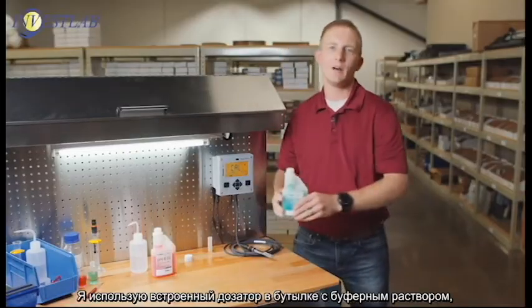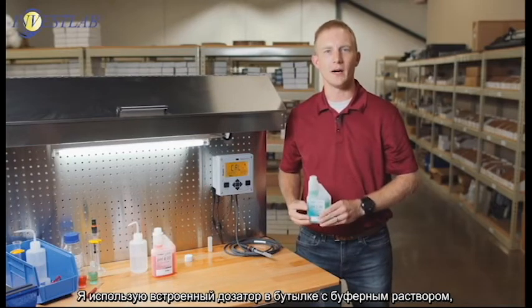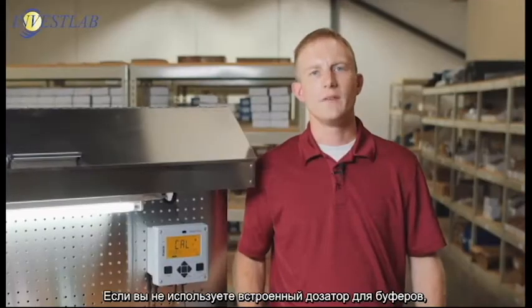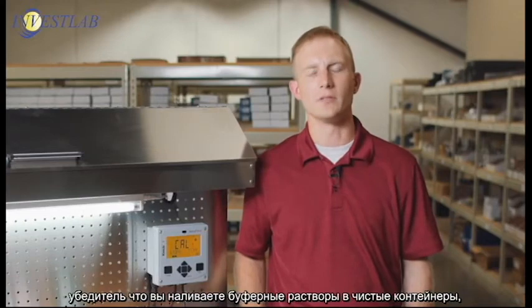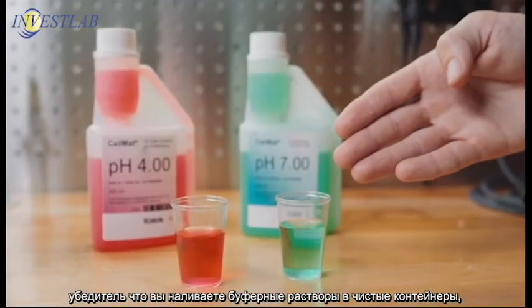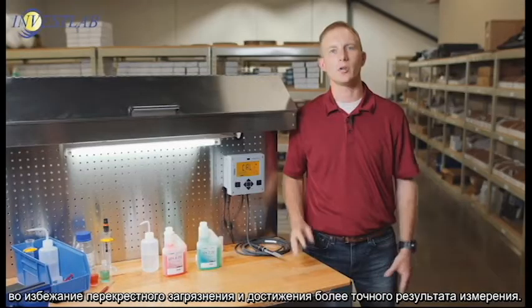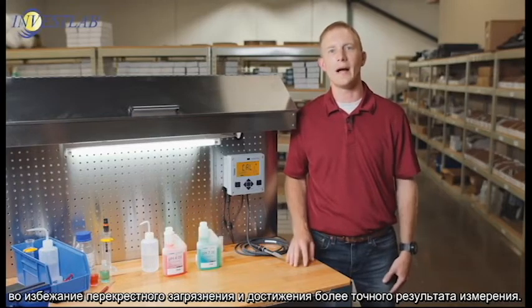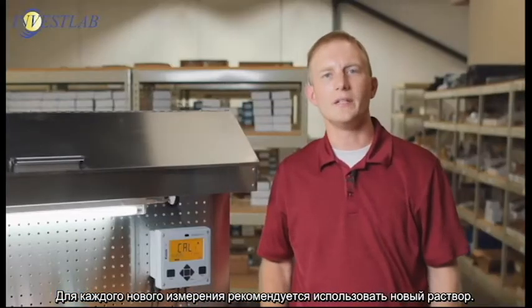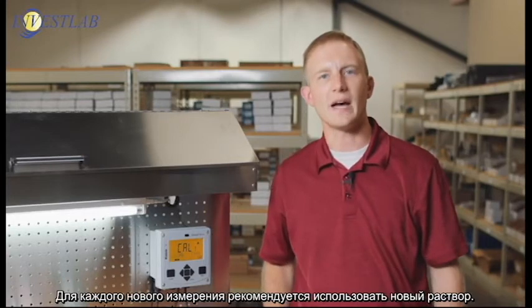I'm using Knick Calamat buffers with integrated dosing cup for single dose usage. If you're not using Knick Calamat buffers, be sure to put your buffers in separate clean containers to prevent cross-contamination and for a more accurate calibration. It's recommended to use fresh buffer solution for each calibration.